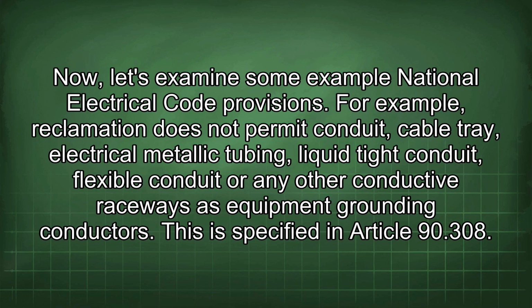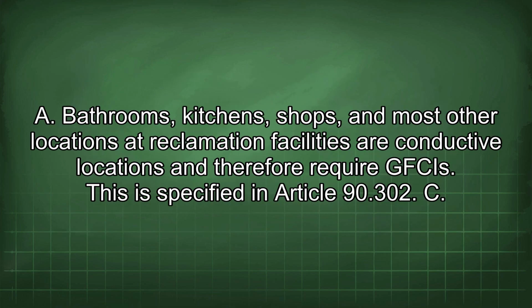Now, let's examine some example National Electrical Code provisions. For example, reclamation does not permit conduit, cable tray, electrical metallic tubing, liquid tight conduit, flexible conduit, or any other conductive raceways as equipment grounding conductors. This is specified in Article 90.308.A. Bathrooms, kitchens, shops, and most other locations at reclamation facilities are conductive locations and therefore require GFCIs. This is specified in Article 90.302.C.